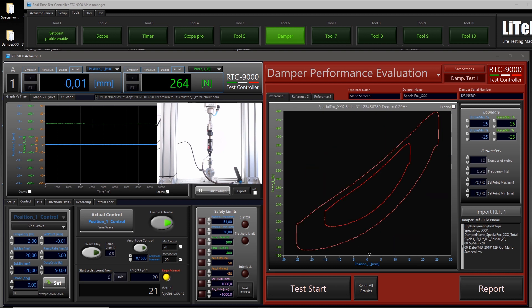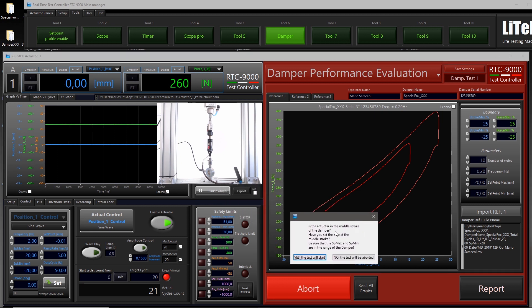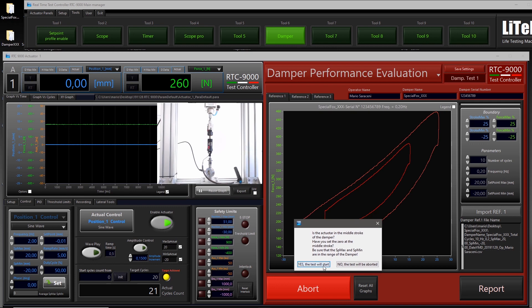Now we can start the test. If the actuator is cold it is better to do a warm-up first, but here the warm-up is already done. The software again asks: is the actuator at the middle stroke? Have you set the zero of the middle stroke? Are the set points within the range of the damper stroke? Click Yes — the test will start.